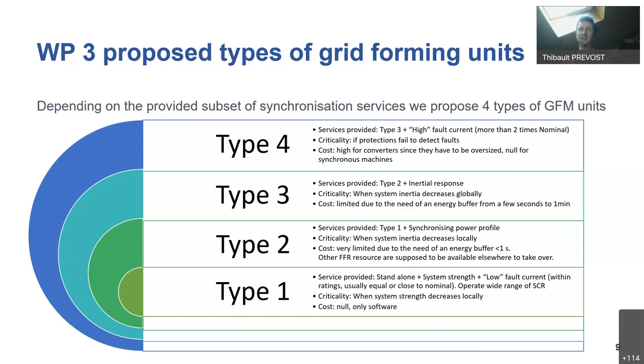Then if you add on top of that some synchronizing power profile, it means when the phase or the angle has a step, you need to provide active current. You need that when the system inertia locally decreases, and the cost is also quite limited because you just need a buffer of energy for one second, let's say. And here again, we assume that all the other frequency services will be delivered somewhere else, or it might be by the same unit, but it's not mandatory.